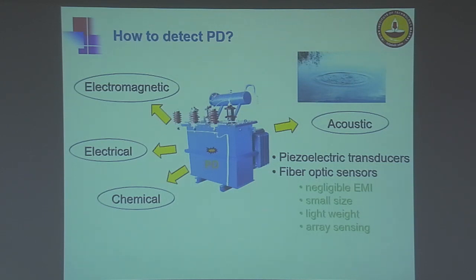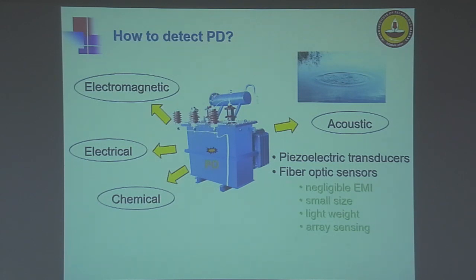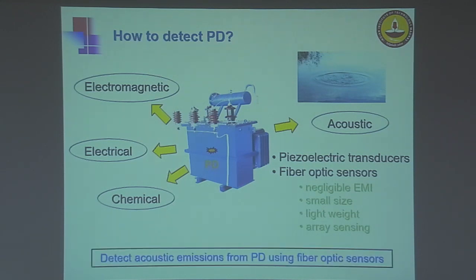Fiber optic sensors are made of dielectric material — that is, glass — making them completely immune to electromagnetic interference. This is highly justified because the transformer is a highly electromagnetically polluted environment, so this immunity helps achieve better sensitivity in our measurements. In addition to being small and lightweight, fiber optic sensors are also amenable to array sensing, which can help in localizing the partial discharge. In short, the focus of our research is to detect acoustic emissions from partial discharges using fiber optic-based sensors.